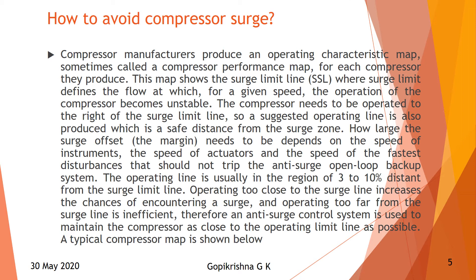There is a region called 3 to 10% distance from the surge limit. You should not always operate near the surge limit, and you should not always operate in the inefficient region. Therefore, an anti-surge control system is used to maintain the compressor as close to the operating limit as possible.